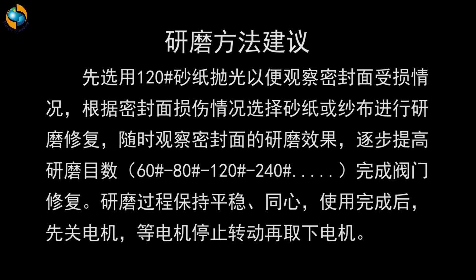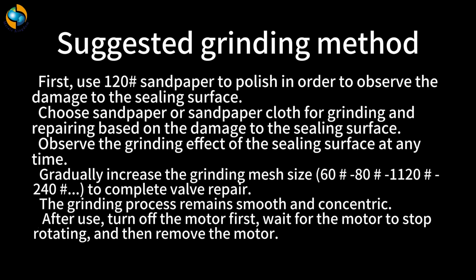Suggested grinding method. First, use 120 sandpaper to polish in order to observe the damage to the sealing surface. Choose sandpaper or sandpaper cloth for grinding and repairing based on the damage to the sealing surface. Observe the grinding effect of the sealing surface at any time. Gradually increase the grinding mesh size, 60 to 80 to 120 to 240, to complete valve repair. The grinding process remains smooth and concentric. After use, turn off the motor first, wait for the motor to stop rotating, and then remove the motor.